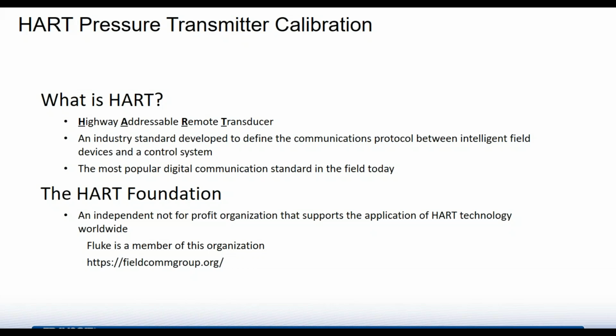So HART, what is it? Well, it stands for Highway Addressable Remote Transducer, which has all kinds of ideas running in the head, but basically what it is, it's a digital protocol which allows you to communicate with the transmitter through the 4-20 milliamp line. It's used widely in process nowadays, and as many companies replace the old analog transmitters, they'll put in a HART transmitter. So that's why HART's important, and it's good to know how to do a calibration using HART. The HART Foundation is a nonprofit organization that supports HART technology. Fluke's a member of it. Many of the transmitter companies are, and that's where all those device descriptions go for calibration.